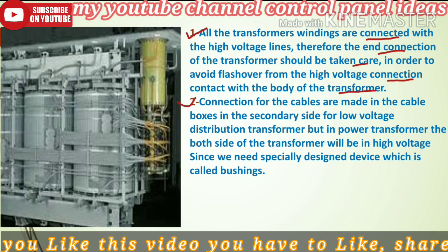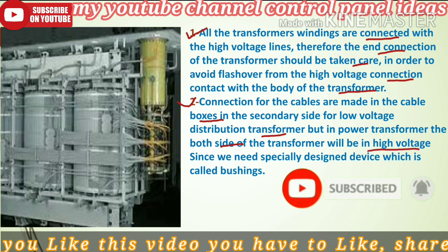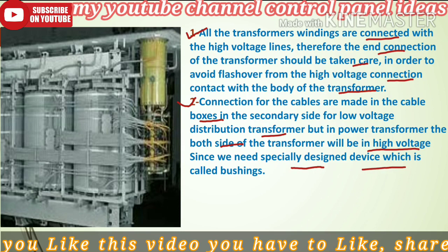Second point, connections for the cables are made in the cable boxes on the secondary side of a low voltage distribution transformer, but in a power transformer both sides of the transformer will be at high voltage. Hence we need a specially designed device which is called a bushing.